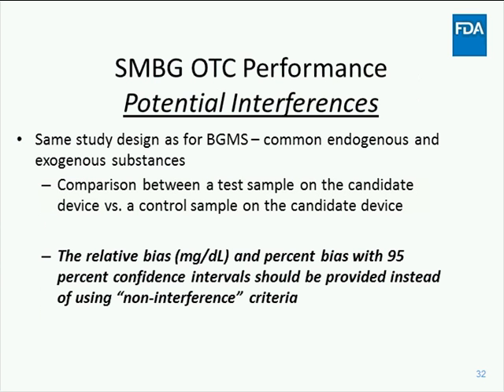The interference testing described in this document is the same study design as outlined in the BGMS guidance, with the testing of common endogenous and exogenous substances that may interfere with the technology and that would likely be present in the user population. As with the BGMS document, the meter results from the test sample are compared to those of a control sample. And the relative bias and percent bias with 95% confidence intervals are provided instead of the non-interference criteria.